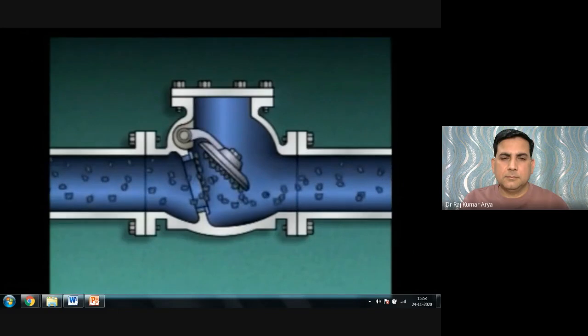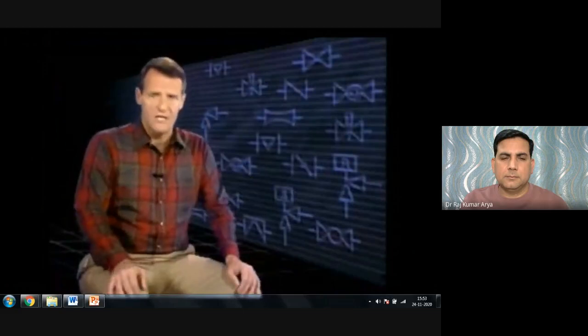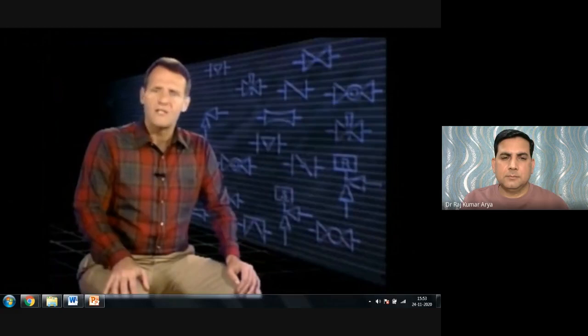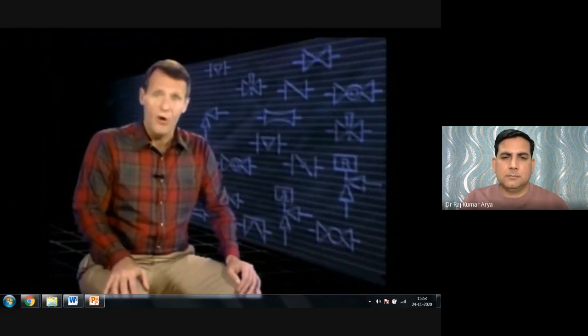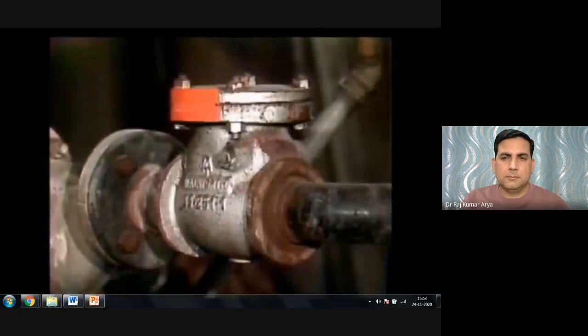Since swing check valves may not close due to buildup of solids on the disc and seat, you should never rely on check valves to isolate a component or system from fluid pressure in another part of the process. This could be extremely dangerous when opening a process system for maintenance. Always shut the appropriate isolation valves to ensure the system is properly isolated.